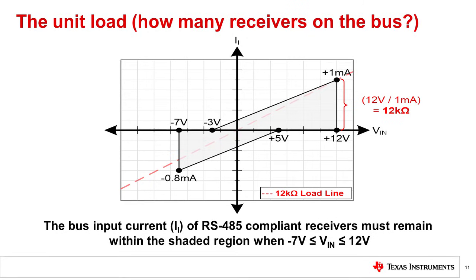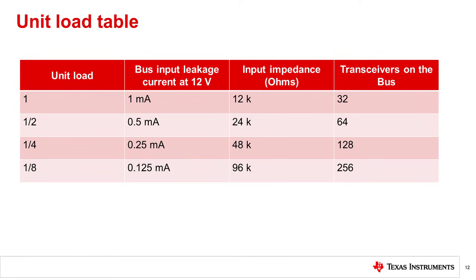TIA/EIA-485A specifies that a compliant RS-485 driver must be able to drive a 1.5 volt differential output voltage across a common mode range of negative 7 volts to positive 12 volts with an equivalent load of 32 one-unit load receivers. One unit load is equivalent to an input leakage current of 1 milliamp at 12 volts, or 12 kilo-ohms. Modern transceivers have higher receiver input impedance, allowing for more transceivers to be present on the bus. The table shown provides the unit loading, bus input leakage current, and equivalent input impedance for the different receiver characteristics. The bus input leakage current is the most reliable way to determine the receiver loading from the datasheet.